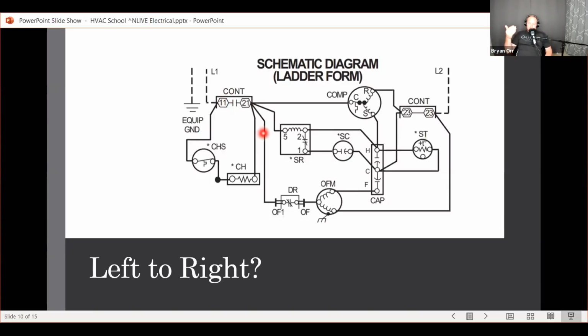Why? Because a voltmeter is a voltage drop measurement tool. I'm not measuring a potential difference between the two, because when there's a closed switch, there's very little resistance between these two points, so there's almost no voltage drop, right? Now, if I open this switch, what is the voltage drop between these two points? Now it's significant, because I have an air gap in between. I've got potential here, potential here, and an air gap in between. That voltage drop is the entire voltage, because the resistance in this air gap is significant. And so now I have 240 volts present across here.